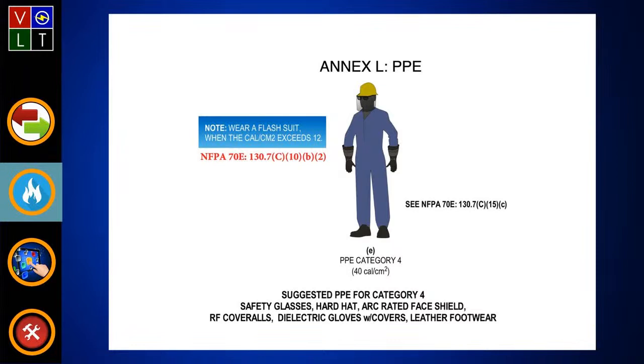Now, looking at 130.7C10B2, it says if you exceed 12 calories per centimeter squared, you have to go to a moon suit, and you can't use the face shield, the balaclava, and dress as that individual is dressing if you're past 12 calories per centimeter squared. And then, of course, the suggested PPE is below for working around equipment.